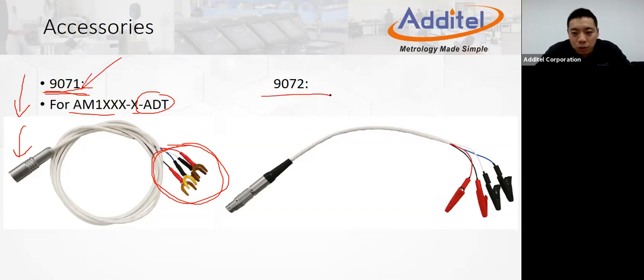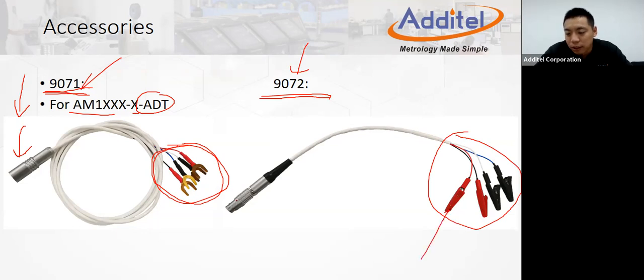The other one is the 9072. This is something customers may always need. For example, if a customer wants to use their own probe as a sensor or DUT, and they want to make a connection to the 282, considering the 282 can only read the smart connection, what they need is this 9072. The regular probe only has a bare wire or spade plug like this. With the 9072, they can use the clamp to connect with the probe - the bare wire right here, and then we have a smart connection right here, and the 282 connects on this side.